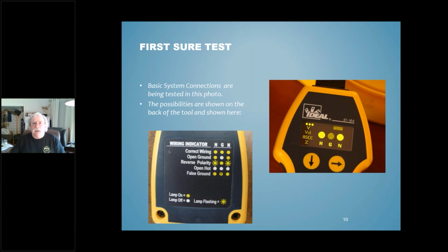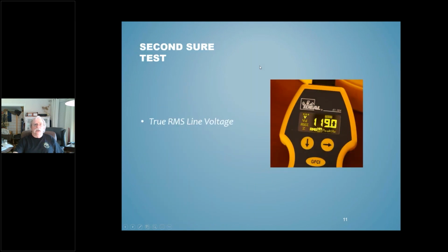So you've got that, and then the front of the machine or meter is actually showing you the light configuration, the LEDs, and once you get through this point, you just hit the down arrow button, and it'll immediately show you the true RMS line voltage at the point at which you're checking it. So here we have 119 volts. I mean, understand that you're not always going to get 120 volts. You won't.